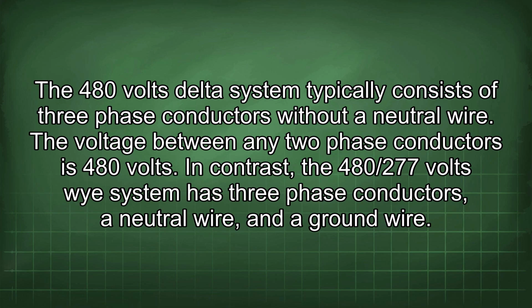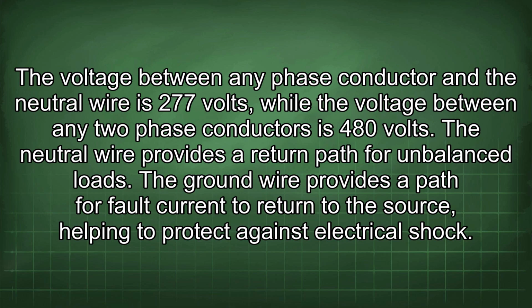In contrast, the 480/277 volts Y system has three-phase conductors, a neutral wire, and a ground wire. The voltage between any phase conductor and the neutral wire is 277 volts, while the voltage between any two phase conductors is 480 volts. The neutral wire provides a return path for unbalanced loads. The ground wire provides a path for fault current to return to the source, helping to protect against electrical shock.